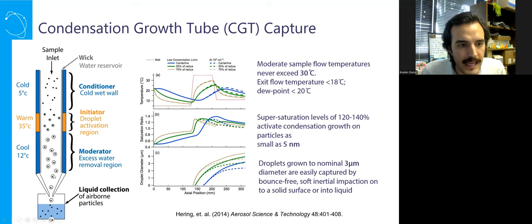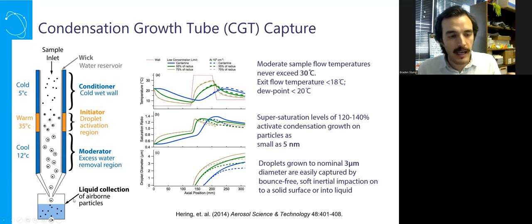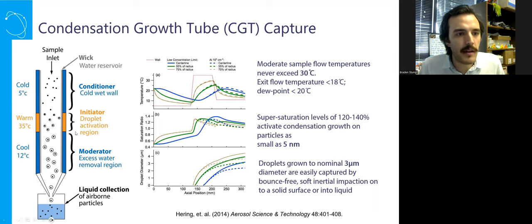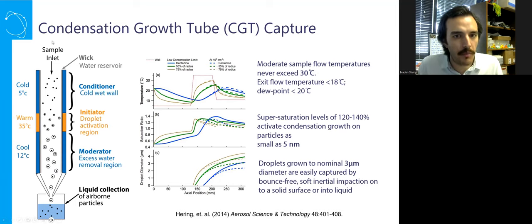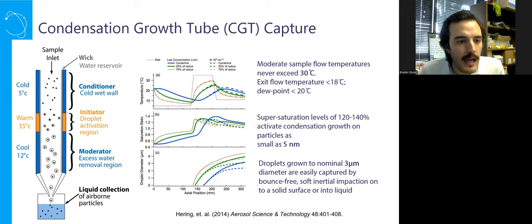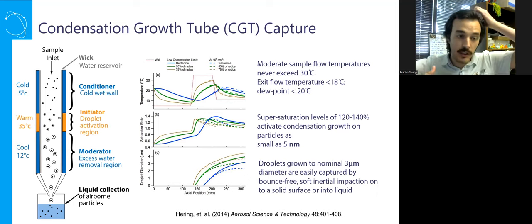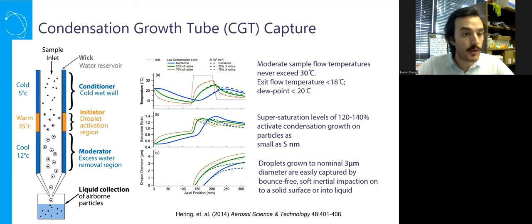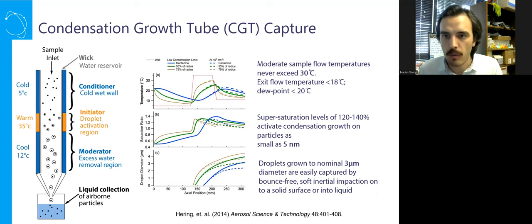Particles as small as five nanometers — in the case of our instrumentation — have condensation forced around them forming a droplet, and that droplet grows throughout the rest of the water condensation growth tube forming a larger, approximately three to four micron droplet. That three to four micron droplet is easier to capture inertially into liquid, onto solid surfaces, onto swabs, onto SEM stubs, TEM grids — the whole shebang. What this is, is a method to grow and surround particles in water via effectively natural processes. One huge benefit is that with this blanket of water around the particles, you get really pretty gentle impaction — that bubble of water is taking a lot of the stress of impaction, so you don't have to impact as aggressively.